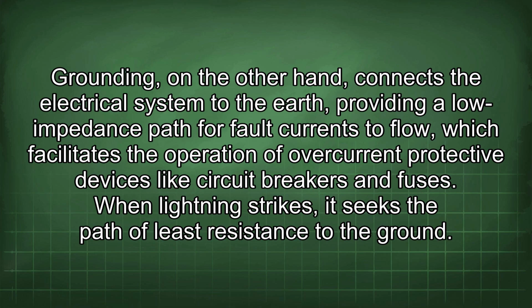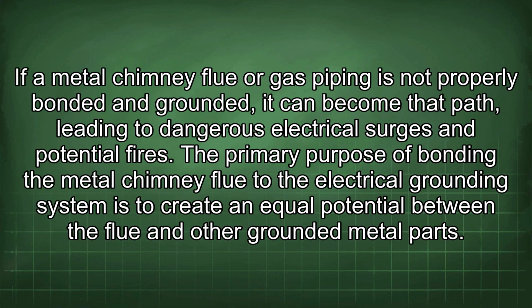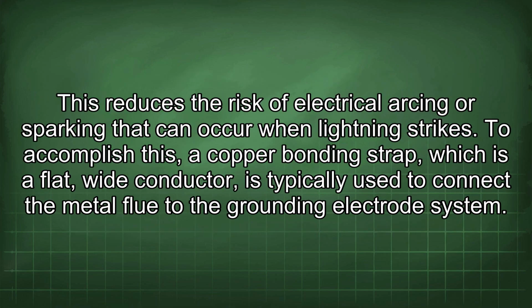When lightning strikes, it seeks the path of least resistance to the ground. If a metal chimney flue or gas piping is not properly bonded and grounded, it can become that path, leading to dangerous electrical surges and potential fires. The primary purpose of bonding the metal chimney flue to the electrical grounding system is to create an equal potential between the flue and other grounded metal parts. This reduces the risk of electrical arcing or sparking that can occur when lightning strikes.